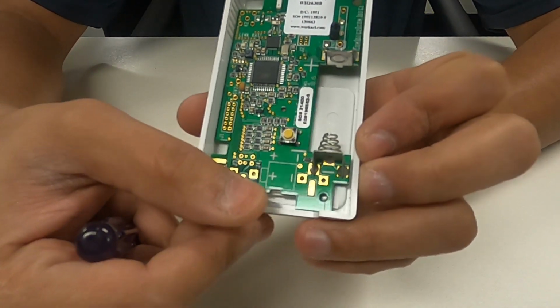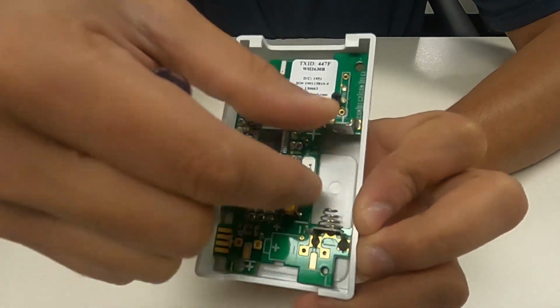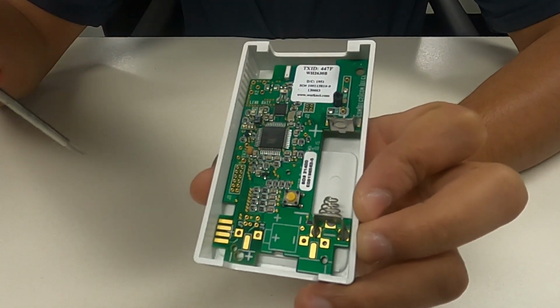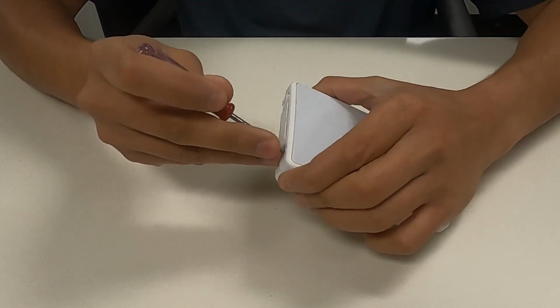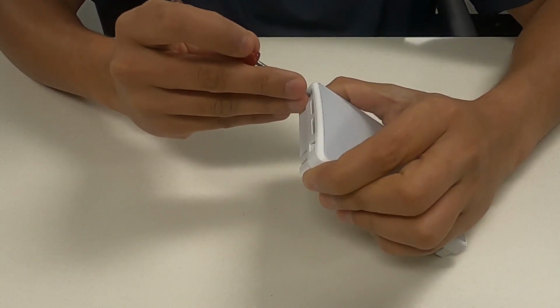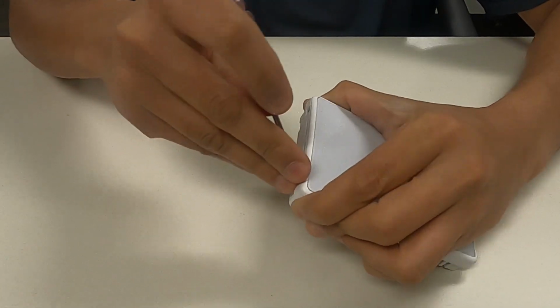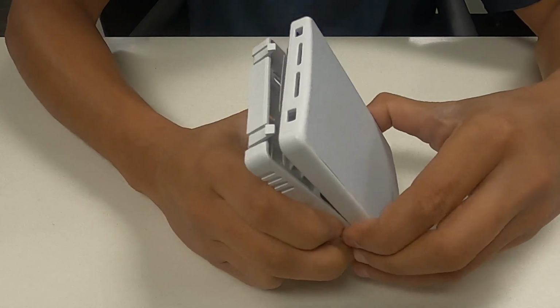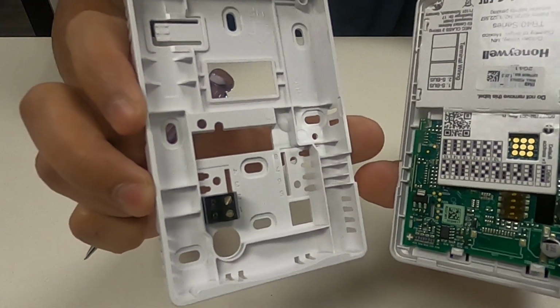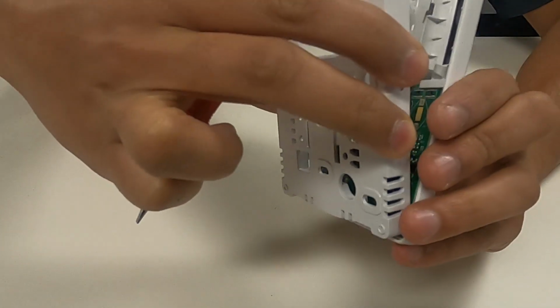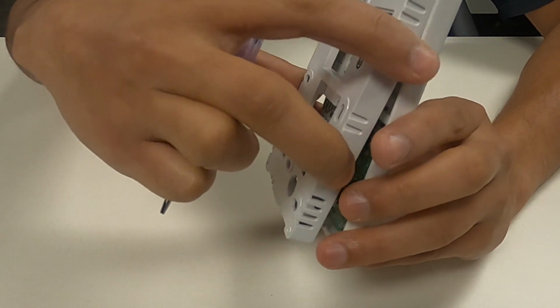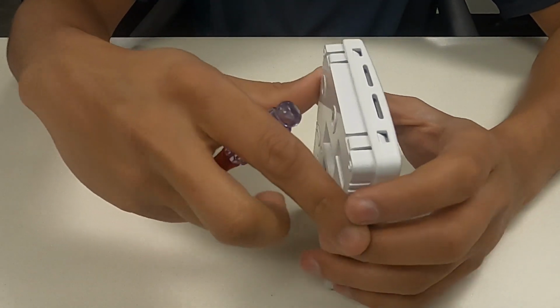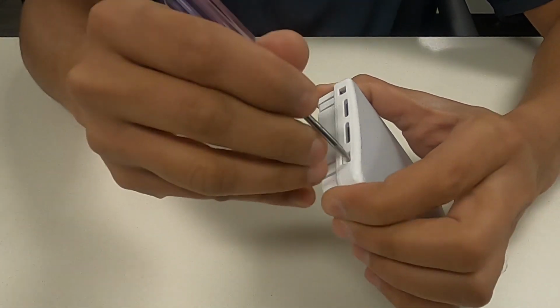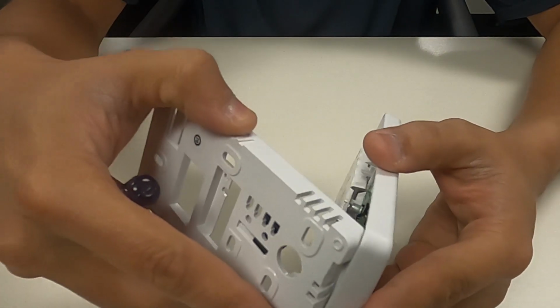Now, here is the selection process for your sensors. If your temperature sensor is a ducted one, based on what do you decide which sensor has to be used? Duct sensors are usually based on how much the duct length is, or if you are using an averaging sensor, it can be however the unit size is. The temperature sensors used in the unit are always averaging sensors in most of the cases. These sensors are spread throughout the coil surface to know the airflow temperature through the unit.